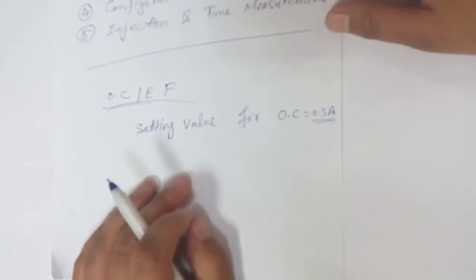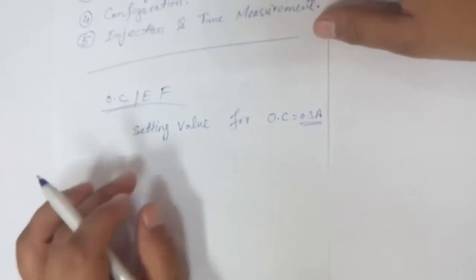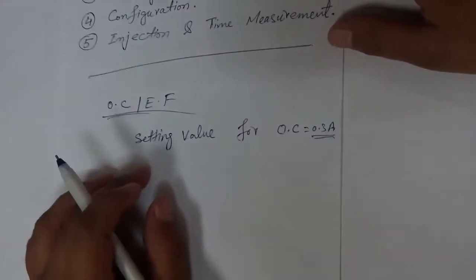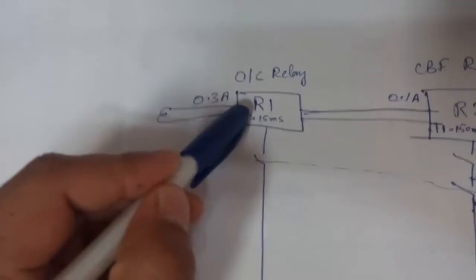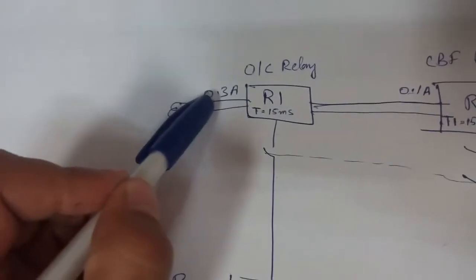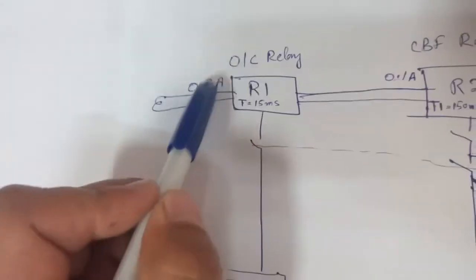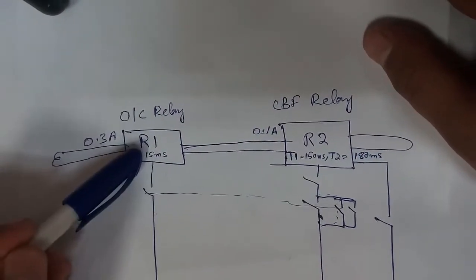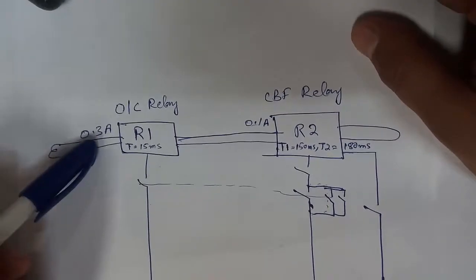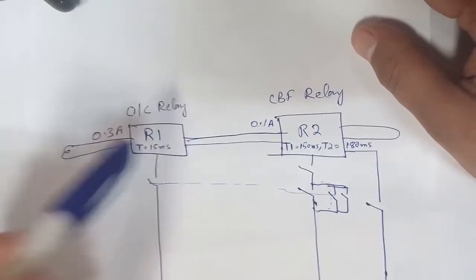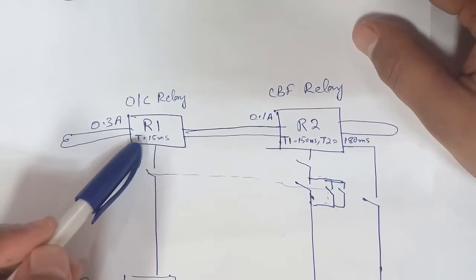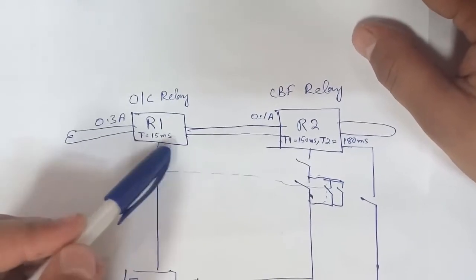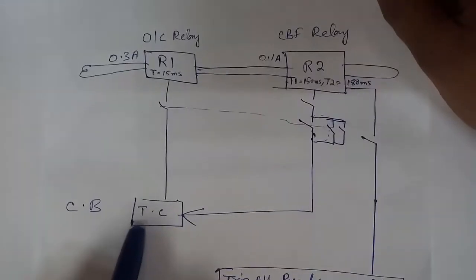For example, we have a setting value for over current of 0.3 ampere. If the current reaches 0.3 or above, it should trip the breaker. We have one current relay named R1 with a set value of 0.3 ampere and one CT. When the current reaches 0.3 or above, this relay will pick up, and after a timer of 15 milliseconds, the contact picks and gives the circuit breaker trip coil the command to trip.